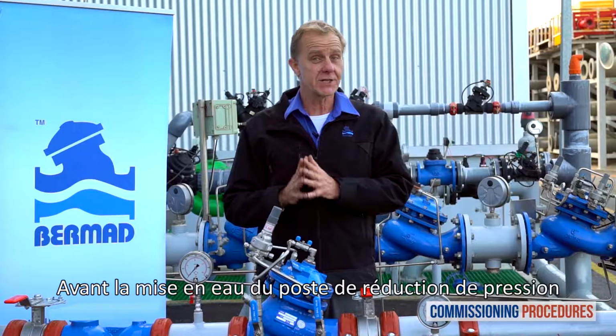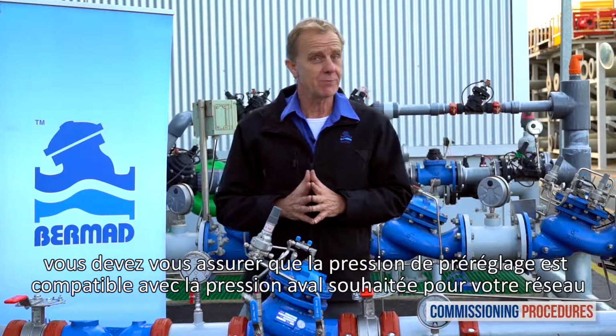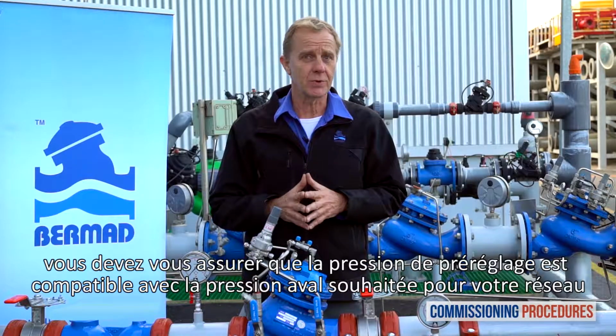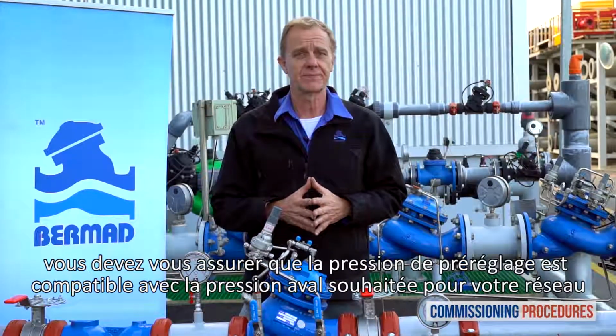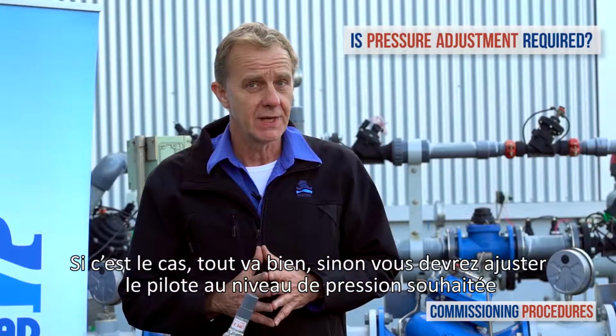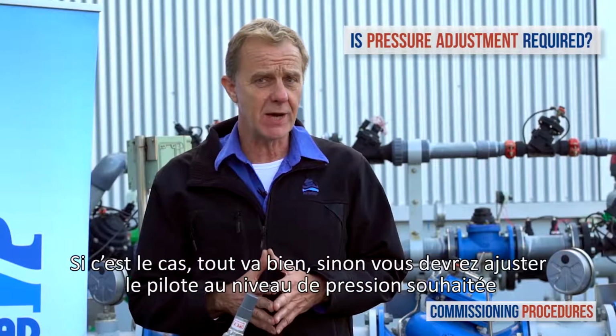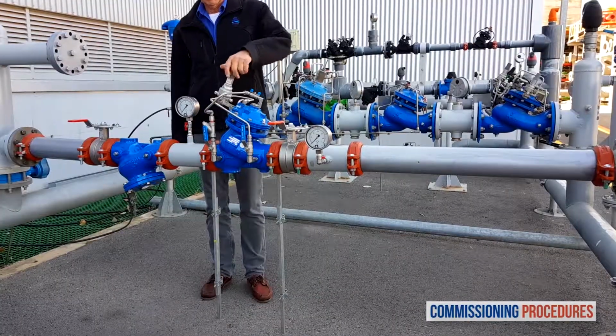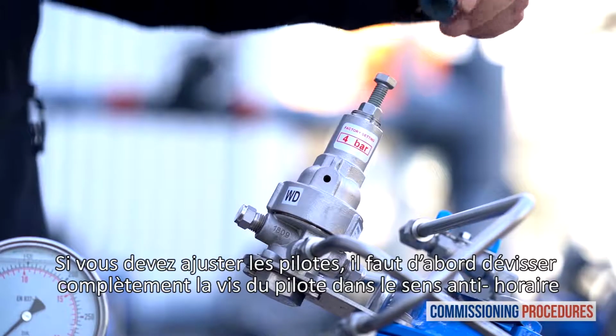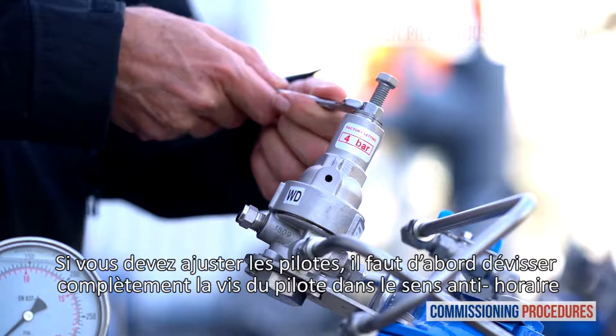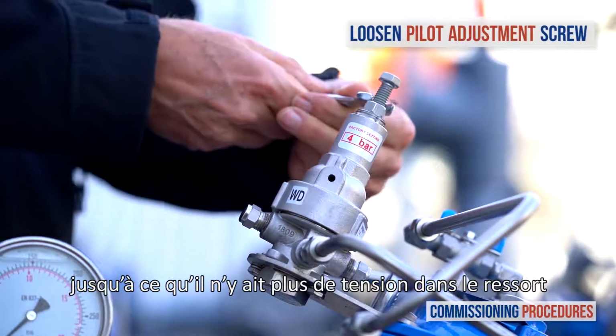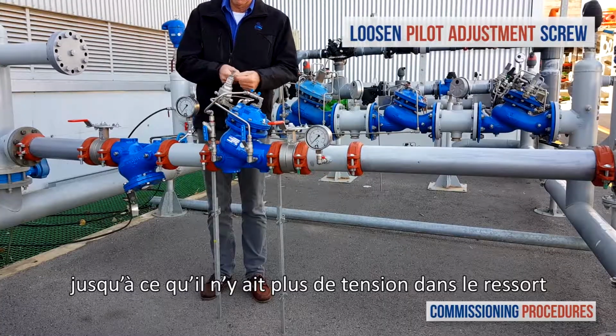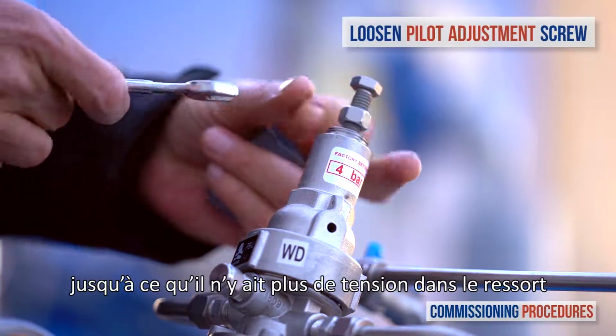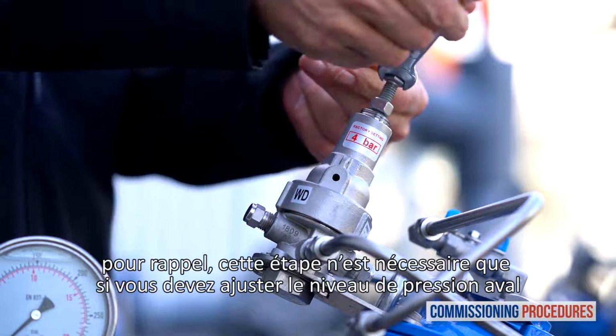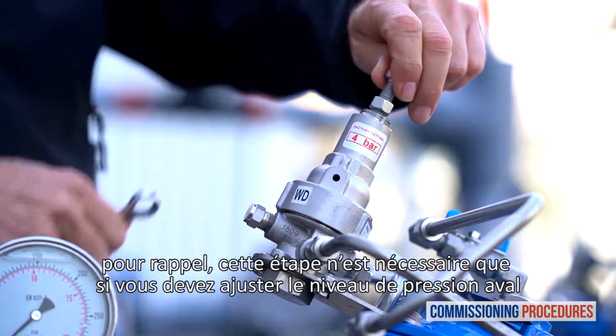Before introducing flow to the station, you need to make sure that its preset pressure level is compatible with your downstream pressure requirements. If this is the case, you're fine. Otherwise, you'll need to adjust the pilot to the required level. If you need to adjust the pilot, all you need to do at this point is to prepare for it by completely unscrewing the pilot's adjustment screw until it becomes loose. Again, this step is only necessary if you need to adjust the unit's downstream pressure level.